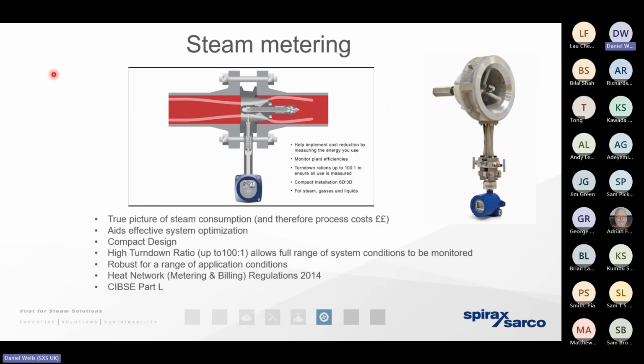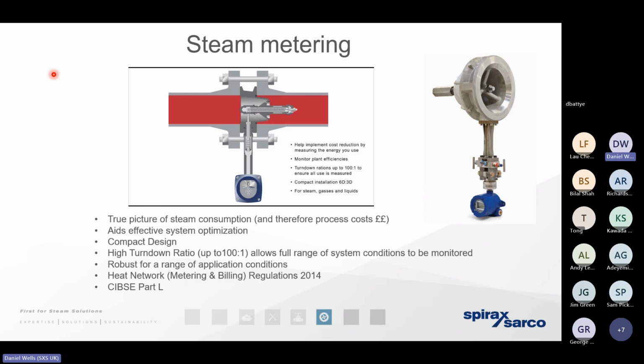So last week we spoke about steam metering being critically important so we can understand the efficiency of the boiler and the cost of steam. But we want to meter the steam when we get it to each individual building or process, because if we know how much steam is going into the pipe and how much is coming out of the pipe, then we know how much is condensing in the middle. In other words, we can use this to tell us how wet or how dry the steam is. We can use it to tell us if we're losing steam as a result of those failed steam traps. But we can also use it for diagnostic purposes.